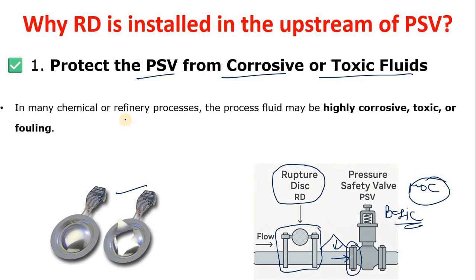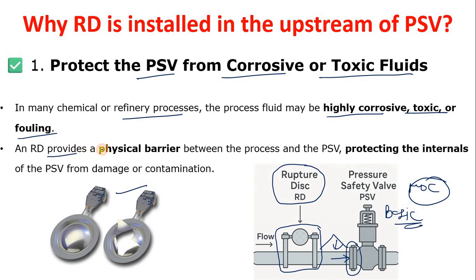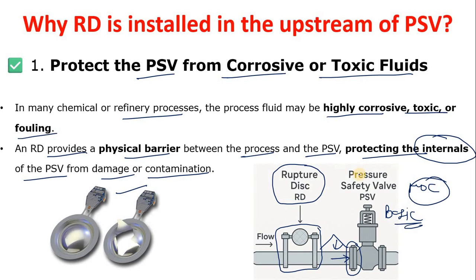In many chemical or refinery processes the fluid may be highly corrosive, toxic, or fouling. An RD provides a physical barrier between the process and the PSV, protecting the PSV internals — such as the seat, spring, and bonnet — from damage or contamination. Over time, if the PSV is leaking and the fluid is corrosive or toxic, the internal parts will also be affected.